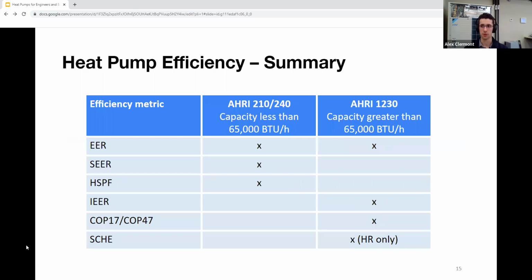So now we just want to talk about a little summary of the different types of efficiencies. AHRI 210/240 publishes the EER, SEER, and HSPF for smaller heat pump systems, so for capacity less than 65,000 BTUs. Now, AHRI 1230, which we'll get into in a little bit, publishes EER, COP at 17 and 47, and SCHE as well. Now, we didn't really talk too much about SCHE, which stands for simultaneous cooling and heating efficiency. But as the name suggests, it looks at simultaneous operation for heat recovery systems. So it actually looks at part of the zones being cooling and heating, which should be looked at for heat recovery systems, as that does make the systems more efficient.